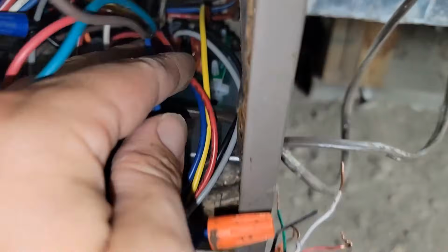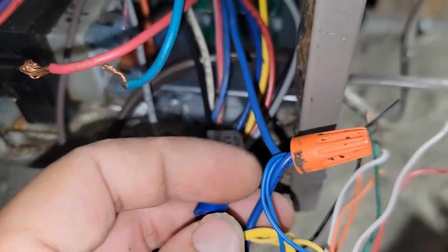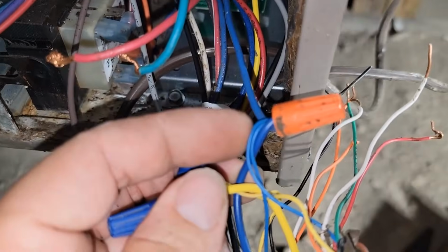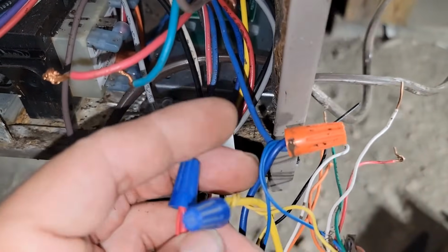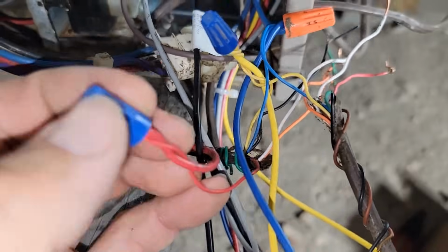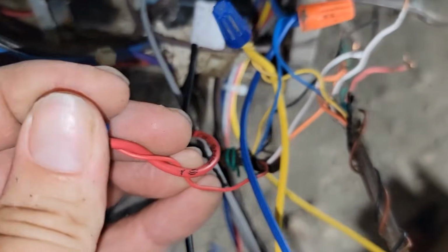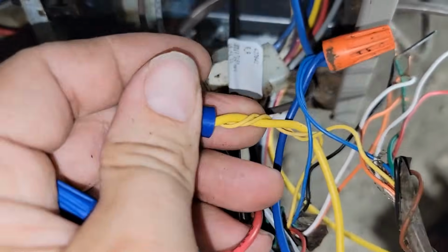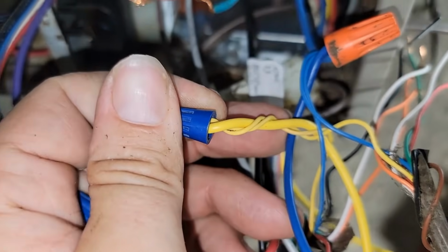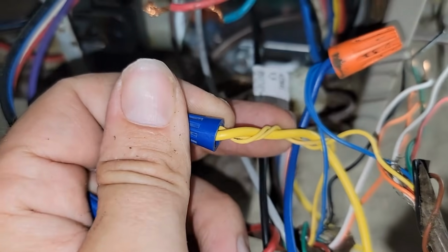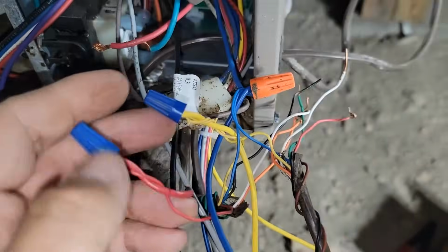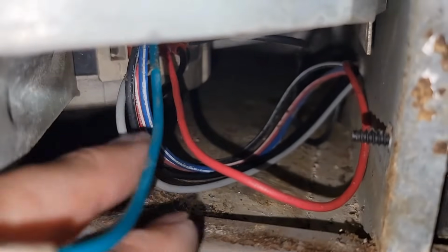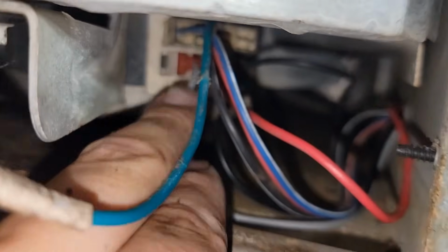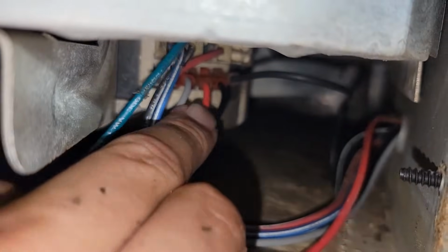All right, so far I've got all the wires hooked up from the relay board, and I'm going to talk to you about how those wires hook up. We had the blue wire from the relay board that hooks into the common, okay? So that's the common from the thermostat to the air handler and to the outdoor unit. Then we had the red wire that comes from the board, goes to the S1 terminal of the outdoor unit, and that's all that does. The yellow wire goes into the first stage cooling call from the thermostat to the outdoor unit, and I'll show you that. And then the last 2 wires were gray and black, and those went to terminal number 2 right there, and then the black wire went to terminal number 4, and those are speed wires.